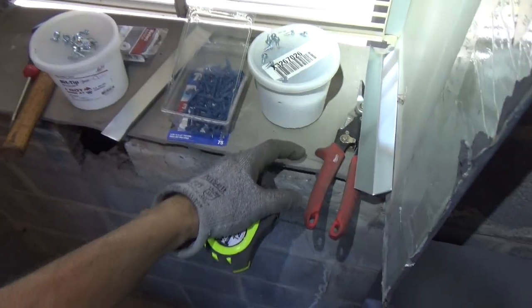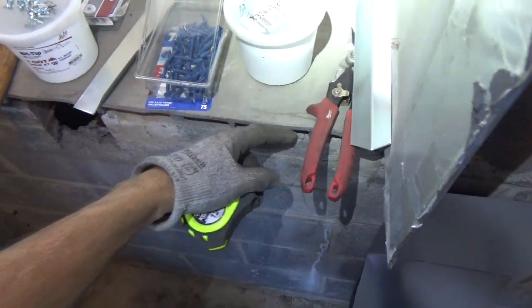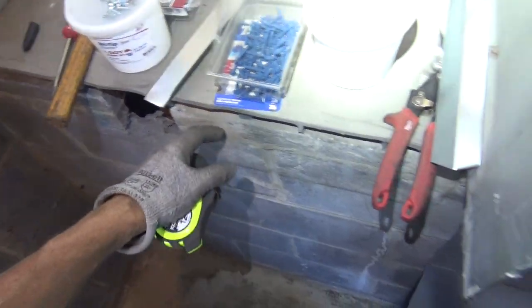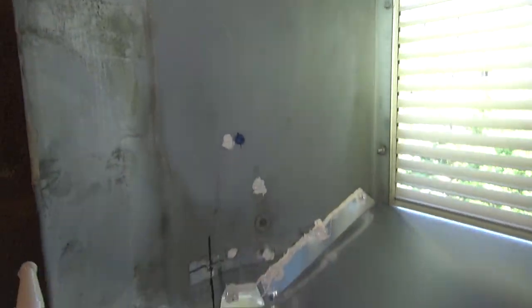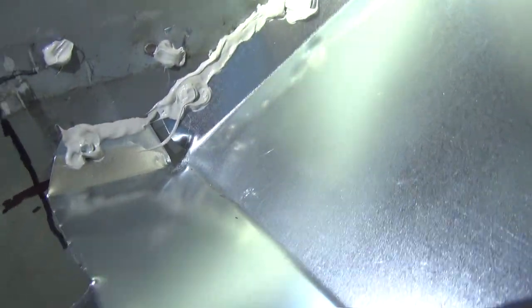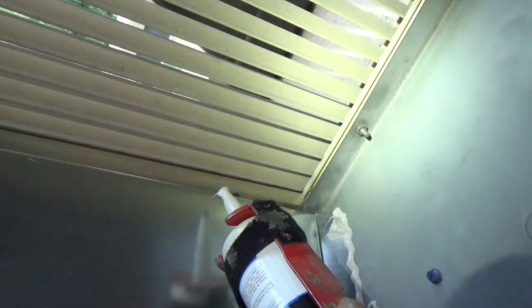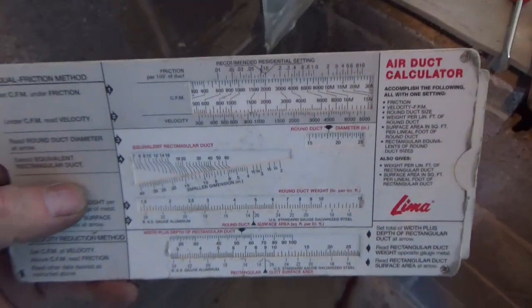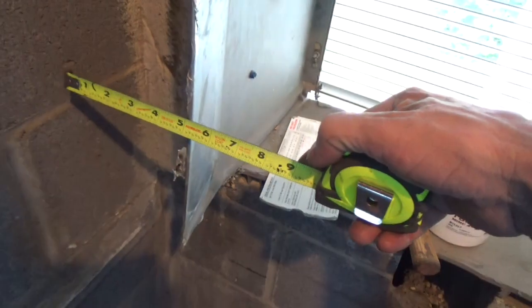So to get airflow on the condenser coil, I'm going to have to knock some of this brick out on the bottom. Caulking up for leaks, but leaving the drain open, and the gutters are caulked as I screwed them in. Then you want to make sure caulk up along the front so you don't get a rattling grill, just like so. Here's the part where you see if your ductwork's going to make it. So I don't have 6 inches.